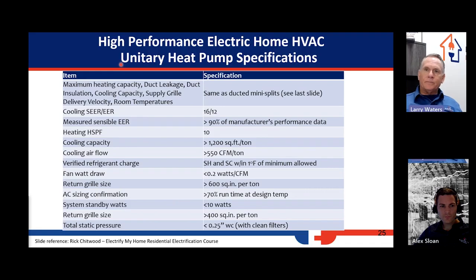Okay, unitary. So same as ducted mini splits. Good unitary high performance is going to give you delivered cooling EER of 12, measured sensible EER of 90% of 12. We always want to have a heating HSPF of over 10. That's hard to get on unitary at 16. Cooling capacity, 1,200 square feet per ton. Most of us aren't shooting for this. Typically, our systems are between 695 and 1,000 square feet per ton, and we're only doing retrofits.